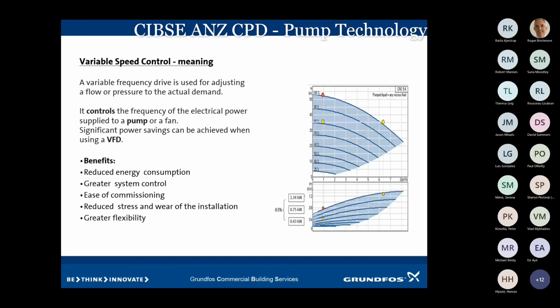But at minimum demands, it's only looking for 1 cubic meter an hour. So we can actually slow the pump down, maintaining a constant pressure. Instead of driving high up on the curve to the red point, we're actually flatlining. We're maintaining the same pressure and we're producing at a lower speed. We've actually dropped our speed to about 80%.